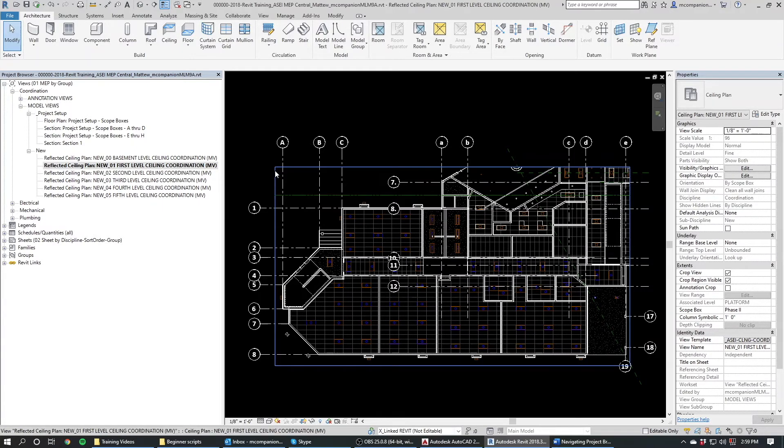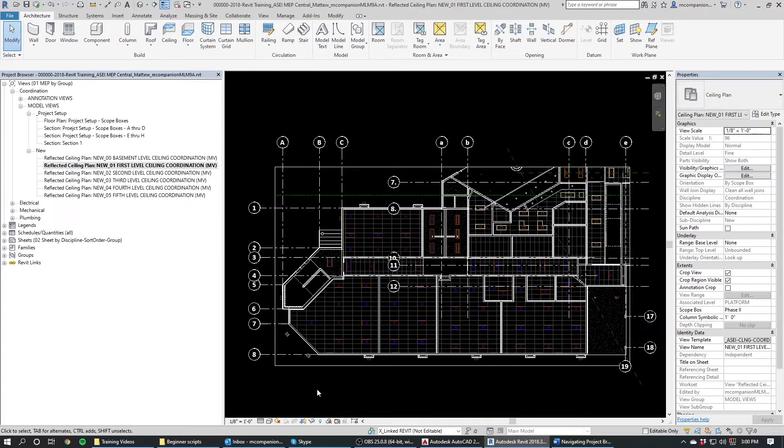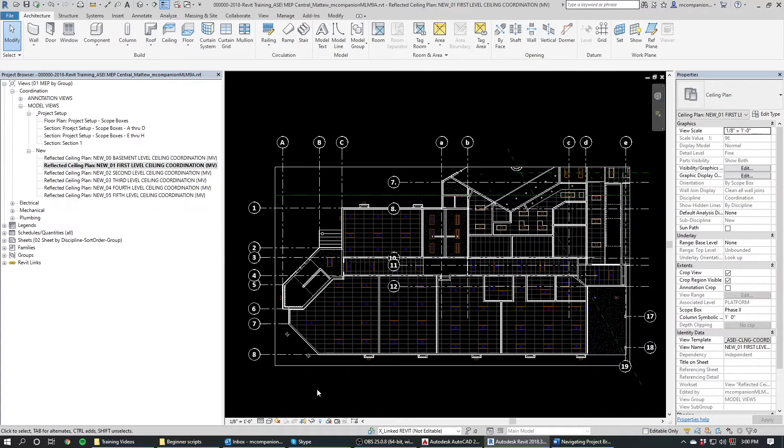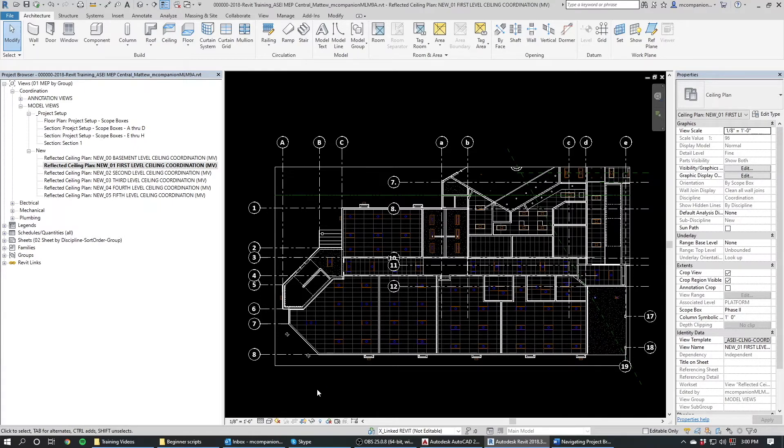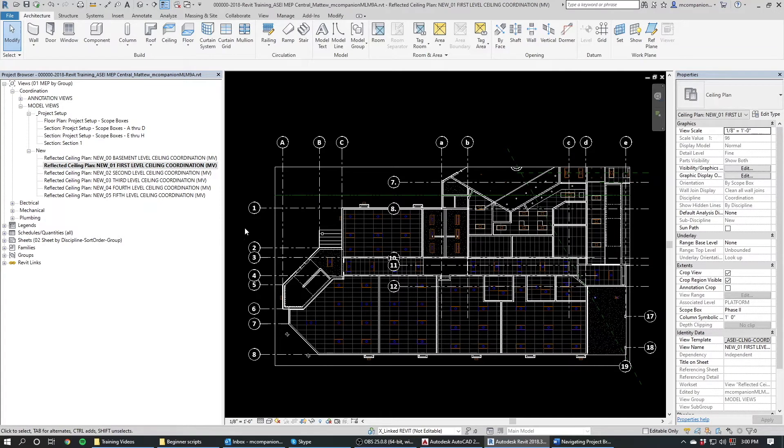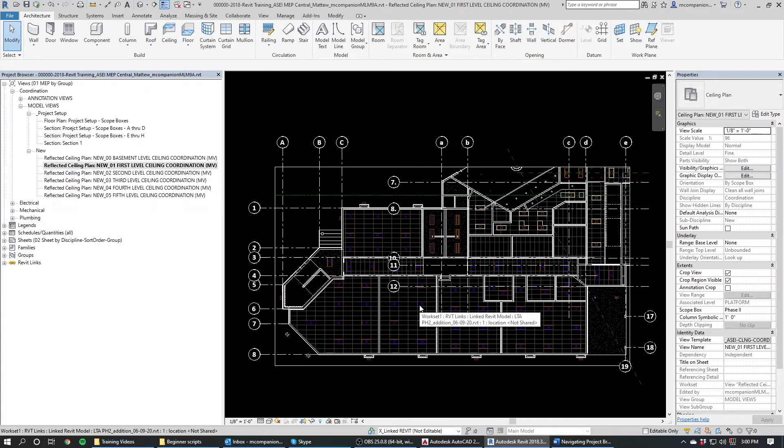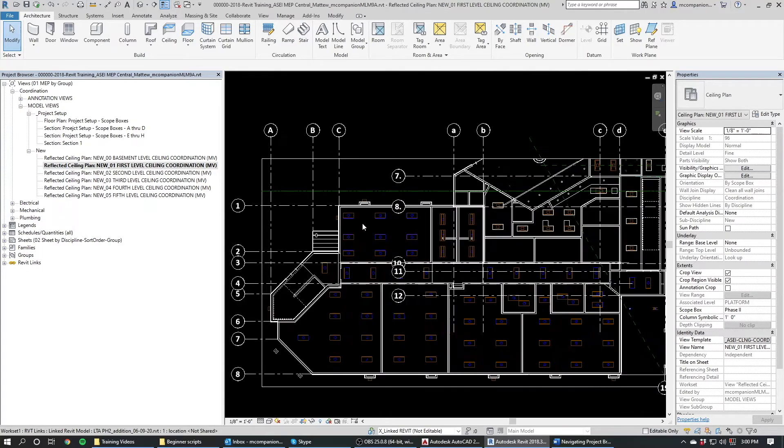Also, we do not use currently, we don't use a ceiling plan in our mechanical sheets because in Revit when you have a ceiling plan, the view is from standing on the floor looking up. So when you draw all your ductwork and you do a hidden line and all of your lines break for depth effect, which is what we do, all of your breaks are backwards. It'll be the wrong way for what you want. So we show them on the floor plan. We draw all of our ductwork on the floor plans so that the breaks are correct. And we put the diffusers in here, which will also show up on your floor plan. You will have diffusers. It's just you won't have a ceiling grid on the mechanical plans. You got to come in here to get your ceiling grid to place your diffusers.